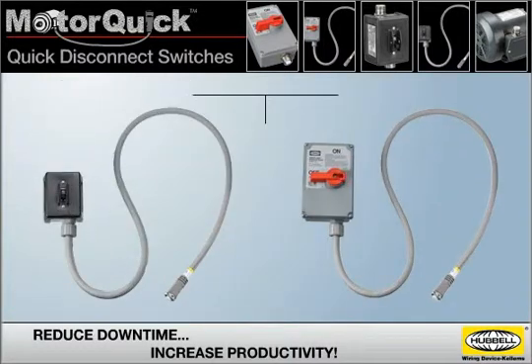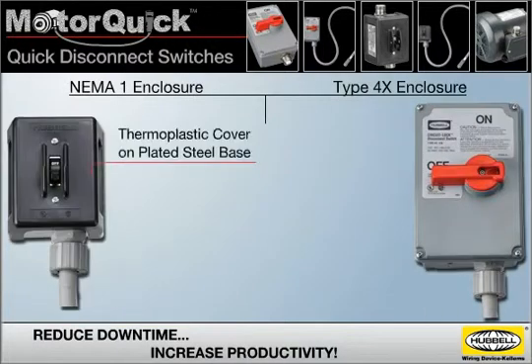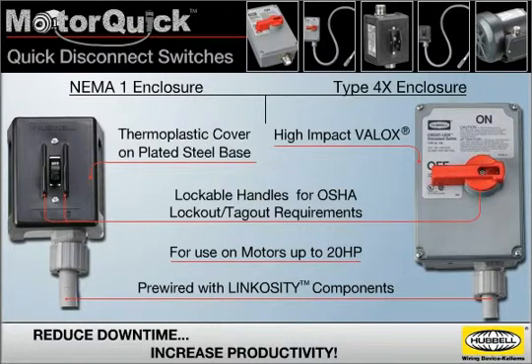CircuitLock Motor Disconnect switches are available in either NEMA 1 or Type 4X enclosures. NEMA 1 enclosures feature a thermoplastic cover on a plated steel base, while Type 4X enclosures are made of high-impact VALOX. Both enclosures come pre-wired with LINKOSITY components, can be used on motors up to 20 horsepower, and feature lockable handles to meet OSHA lockout tagout requirements.